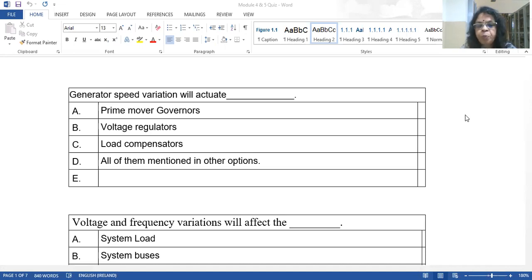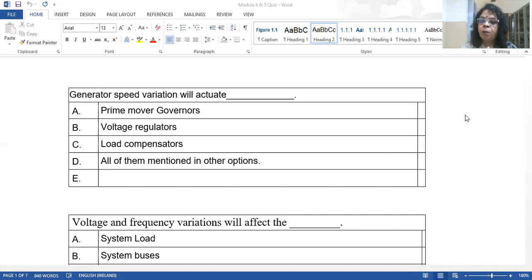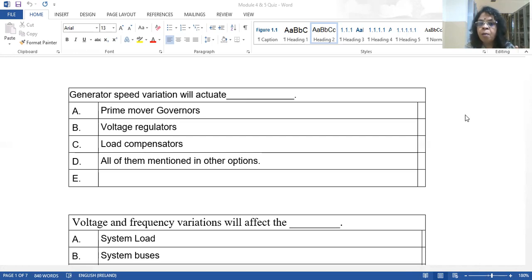Generator speed variation will actuate — let's also summarize what we've learned. Whenever the generator speed changes, the frequency also changes. To maintain speed at the nominal value, we need to balance the active power. Active power is controlled by the turbine input in conventional generators, and the turbine input is controlled by the governors of the turbine.